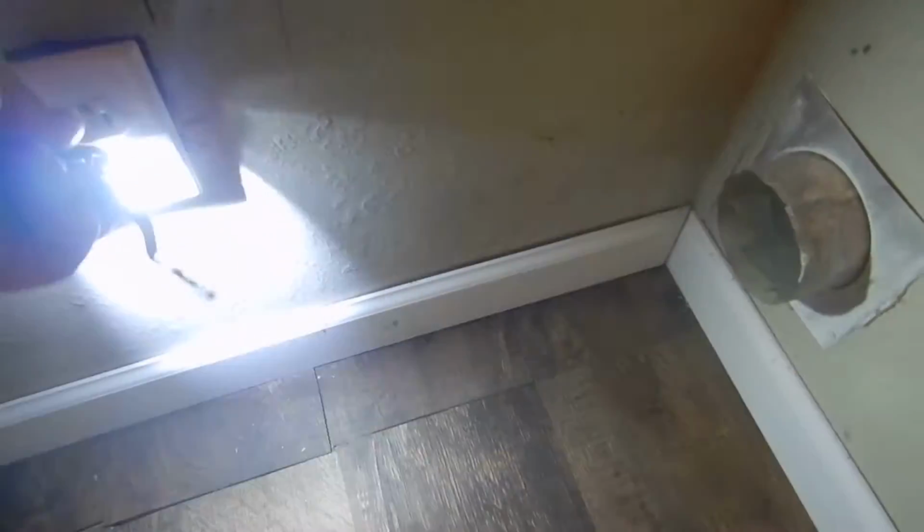We do. And both of the water heaters are old. It's time to replace them, and they've got their own issues. Clothes dryer is 3-prong, and then we've got gas. Gas not in use should be capped off. By today's standards, this would be GFCI protected, and that would be GFCI protected. And this guy just fell out of the wall. Somebody added him, I guess, for the gas. I don't know. Somebody decided we wanted that. There's no ground. That guy, he doesn't have any grounding.